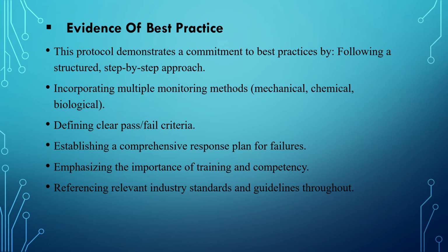This protocol demonstrates a commitment to best practice by following a structured step-by-step approach from cleaning to sterilization, and recording all the information that we can obtain, and also monitoring the printout, BIs, and chemical indicators, and the hydrogen peroxide expiry date, and so forth. Incorporating multiple monitoring methods: mechanical, chemical, and biological indicators. Here we also monitor all that information. Defining clear pass or fail criteria.